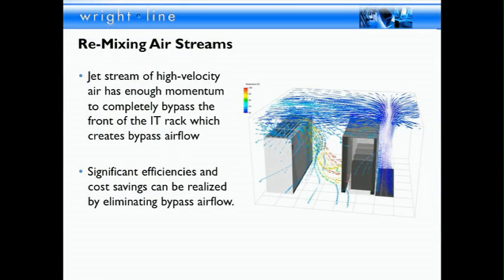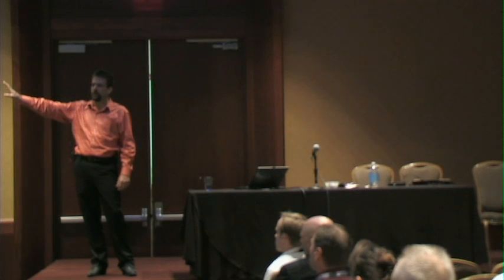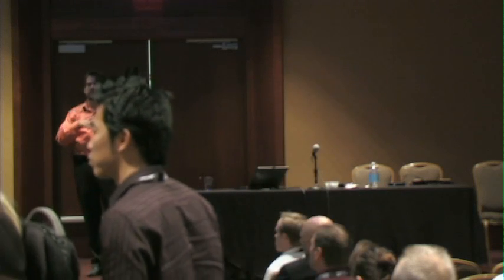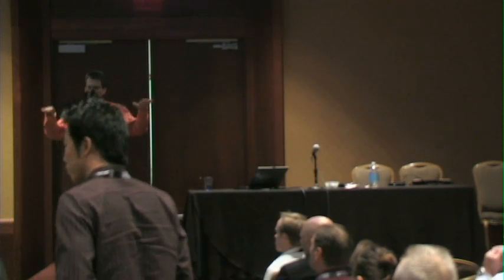Well, that bypass airstream could actually be causing that. That bypass airstream is cool air that is coming out in a jet stream fashion from a perf tile, hitting the ceiling, creating what is essentially a mushroom cloud of cool air, half of it moving warm air away, the other half of it going back to the AC equipment. But when it does that, it disturbs that layering effect that is really required for stratification to work well.